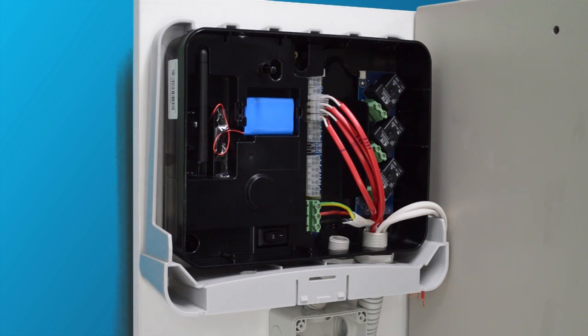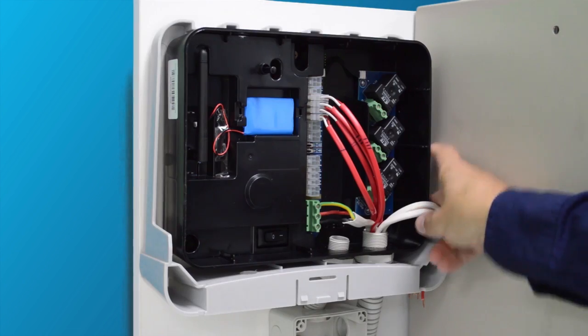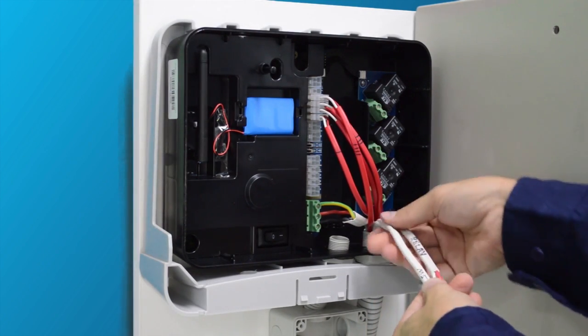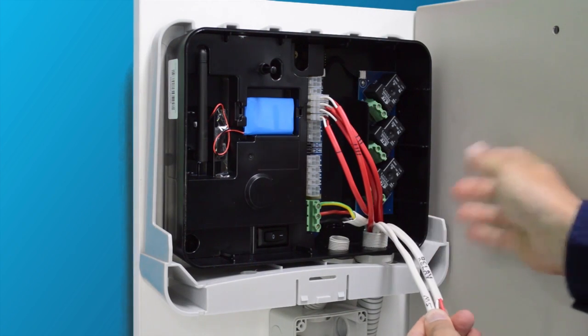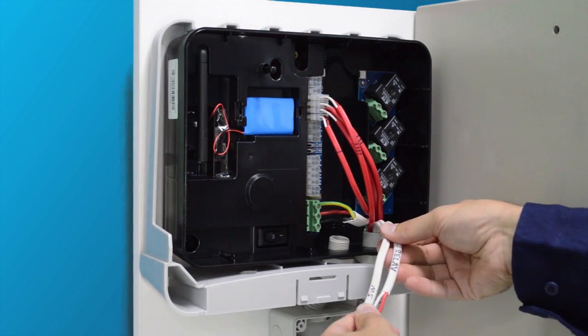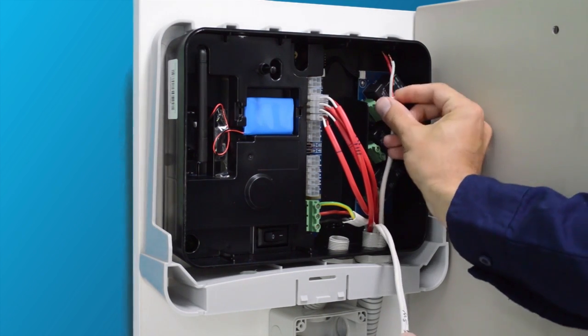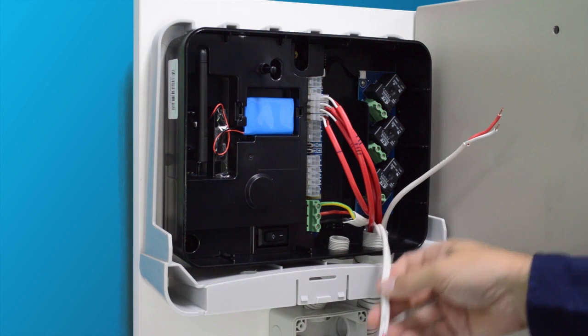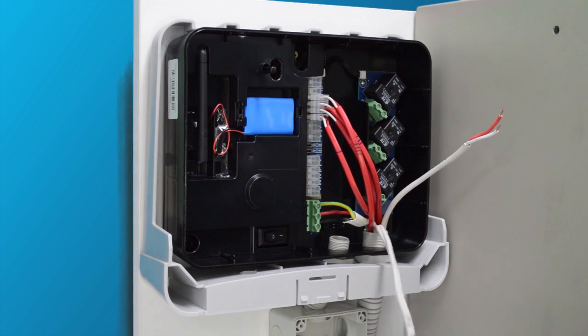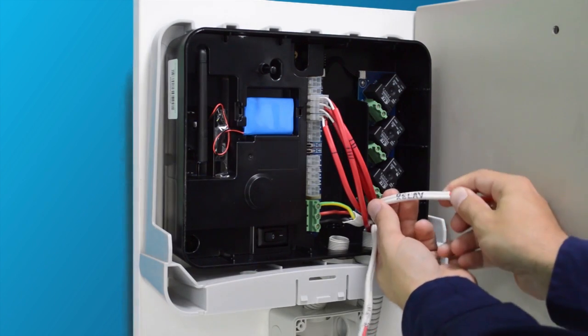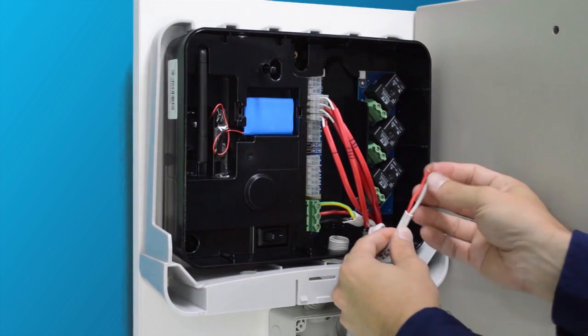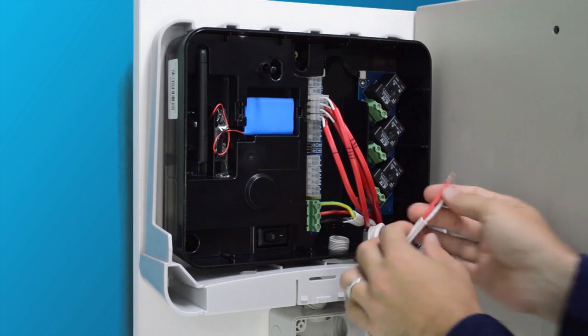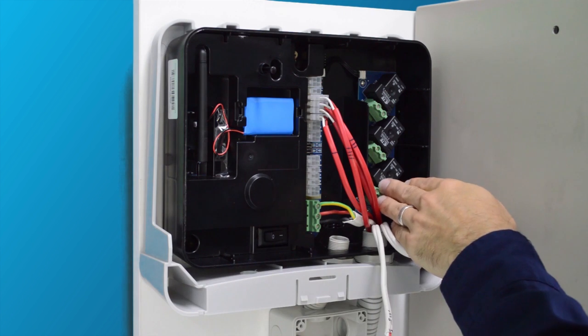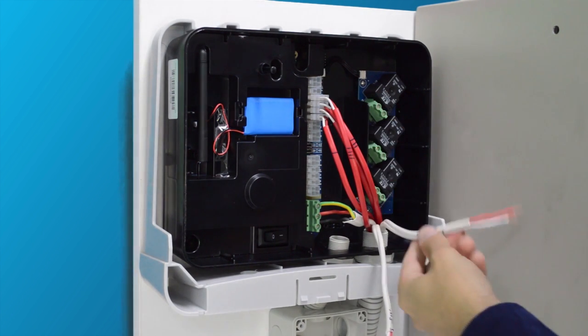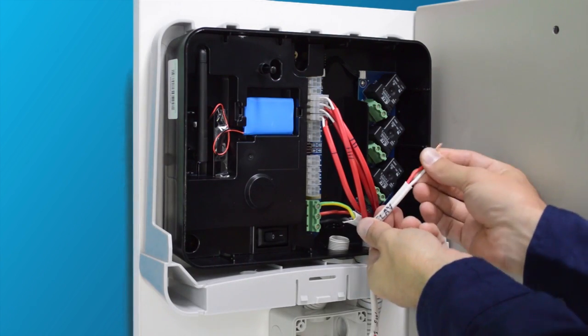I'll now demonstrate switching and bypass switch of an external weatherproof bypass switch at the CT200 side. As you can see, I've run 2 twin actives from the CT200i unit into the switchboard. 1 labelled at both ends relay, which will connect to the carbon track relay, and 1 labelled switch, which will connect to our bypass weatherproof switch. Firstly, to connect switching, connect the cable labelled relay into any one of the 3 carbon track 20 amp normally open relays. Take note which relay has been connected to. They're labelled 1, 2 or 3, as this will become important later on in the testing and commissioning process.